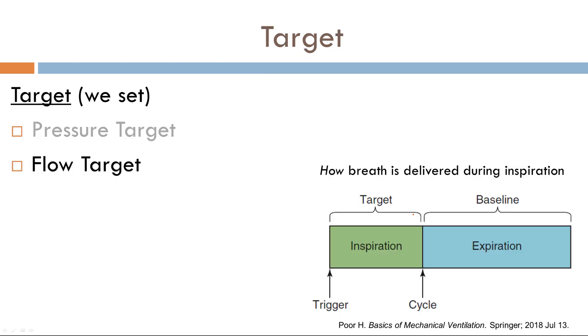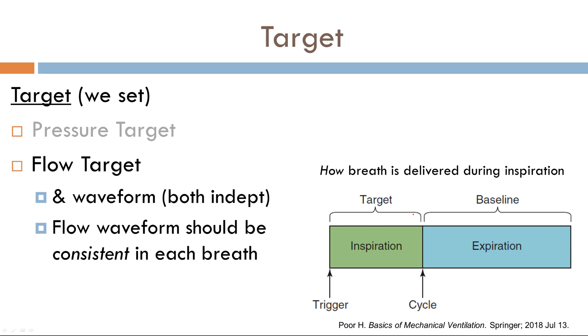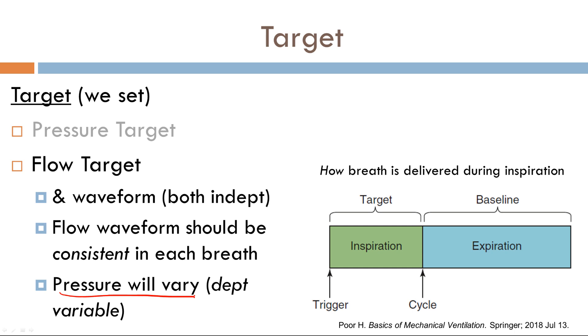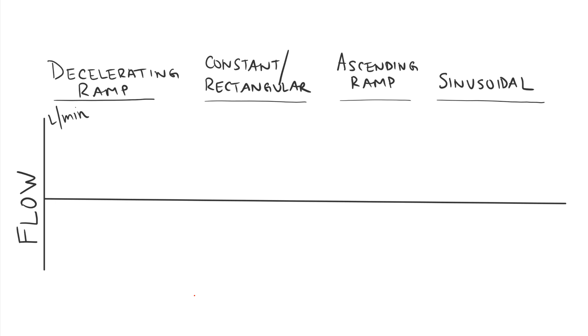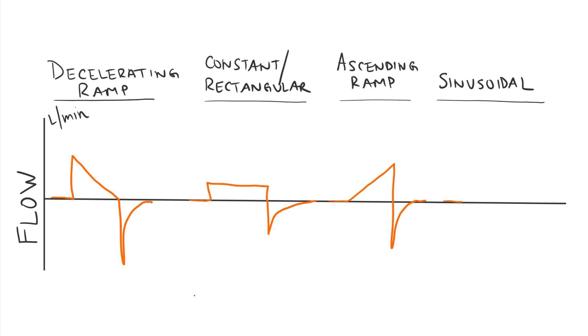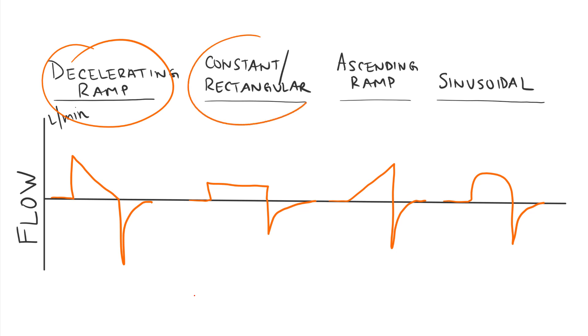Now let's talk about flow target. In flow target, the independent variable is flow — we set the flow as well as the waveform. The flow should be consistent with every single breath. Flow is the independent variable, but what varies is pressure, which becomes your dependent variable. There are a few ways we can adjust flow: we put in a numerical value and also set what the flow ramp looks like. Common ramps include decelerating ramp, constant or rectangular, ascending, and sinusoidal.